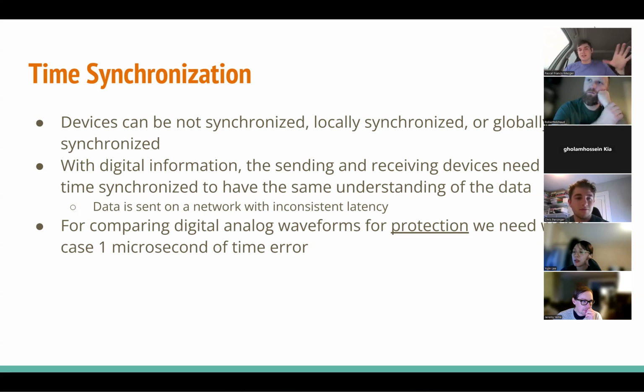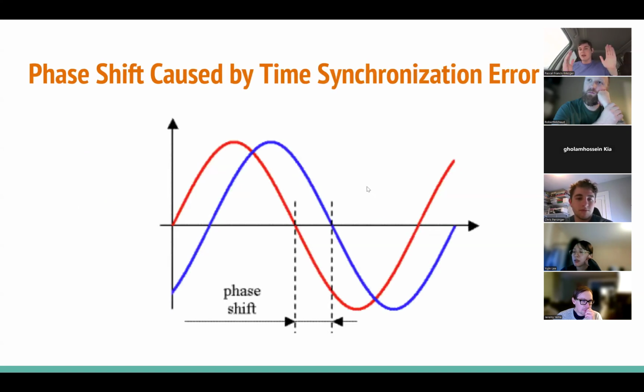That's why we need continuous time synchronization for digital substations. If IEDs aren't continuously time synchronized and they compare voltage waveforms sent on the network, over time they'd get farther apart and create more error. They'll drift farther apart, then synchronize and get closer again, and repeat this over and over. So we need to keep that maximum error under 1 microsecond for a digital substation.